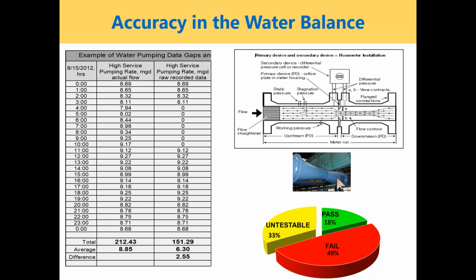There's also a secondary part of the meter, the brain of the meter. That motion has to get translated - in a Venturi meter, the pressure difference gets converted by the register or transmitter; in a mechanical meter, the number of motions gets translated into a pulse, and somehow into a flow reading. That translation happens not in the primary device but in the secondary device. And then, just for conversational purposes, there's also a third device, which can be your SCADA system.